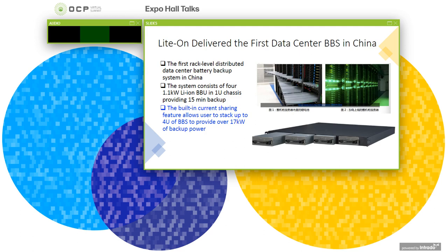Currently, we have a BBS product operating in the field—this is the first rack-level BBS in China. The system consists of four 1.1 kilowatt BBU in a 1U chassis, providing 15-minute backup power time. The built-in current sharing allows users to stack up to 4U of BBS to provide 17 kilowatt backup power. Pretty awesome.